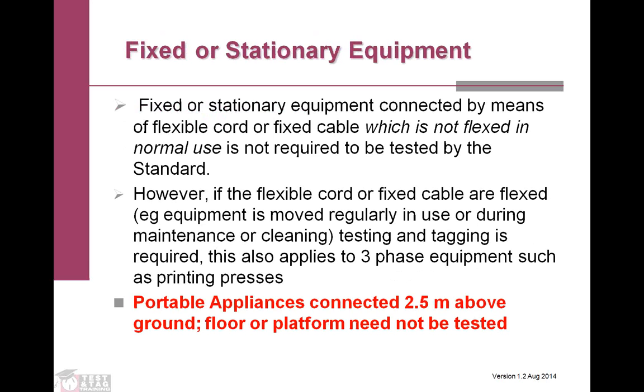Okay, so looking at all the appliances within the workplace, and I'll cover the environments in a couple of slides' time, because some things actually don't require testing all that often, if at all. But essentially, fixed and stationary equipment that's connected by a flexible or fixed cable, which is not flexed in normal use, is not required to be tested. So anything hardwired, in other words. If an electrician's installing a new press out back and hardwiring it, or if it's off a pendant from the ceiling, that type of thing, then it may not need to be tested at all. But if the flexible cord is flexed and the equipment can be moved, then test and tag is normally required.